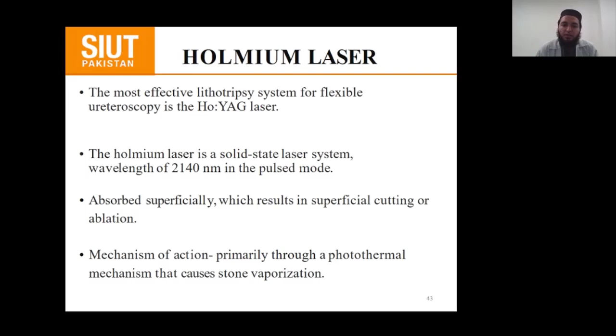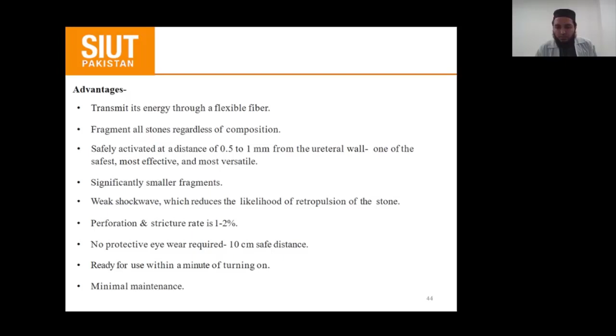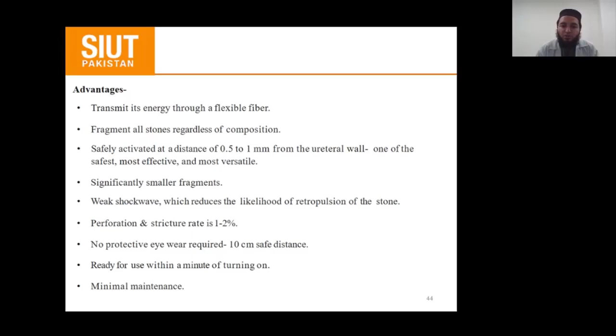There are many advantages of the holmium YAG laser. Few of them are: it transmits energy through a flexible laser fiber, fragments all stones regardless of composition, be it a hard stone or a soft stone with any attenuation values, safely activated at a distance of 0.5 to 1 millimeters from the ureteral wall, one of the safest, most effective and most versatile, significantly smaller fragments, weak shock wave which reduces the likelihood of retropulsion of the stone, perforation and stricture rate is 1 to 2%, no protective eye wear required, that is, it can be used up to 10 centimeters safe distance, ready for use within a minute of turning on the machine, and minimal maintenance is required.